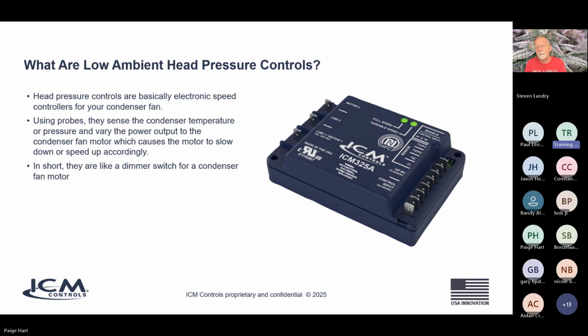And pressure transducers are no different. They just sense the pressure directly and send a little signal back to the ICM control to adjust the output voltage to the motor. So a glorified dimmer switch is a great way to get a general sense of how this thing works. By adjusting the amount of airflow we push past the coil of the condenser, we can maintain and control our head pressure much better than the rapid swings of fan cycling type controls.